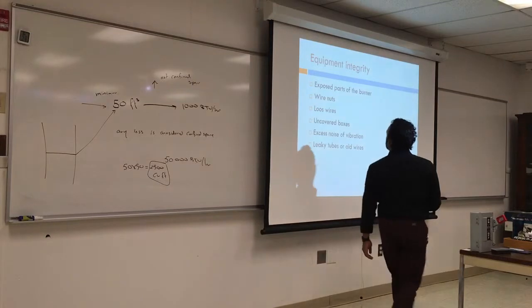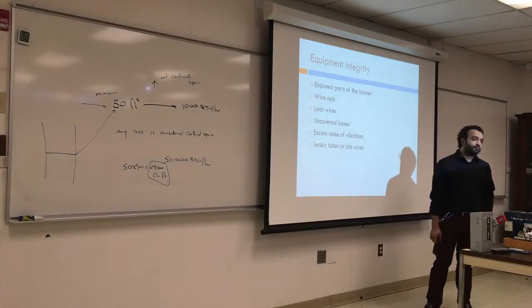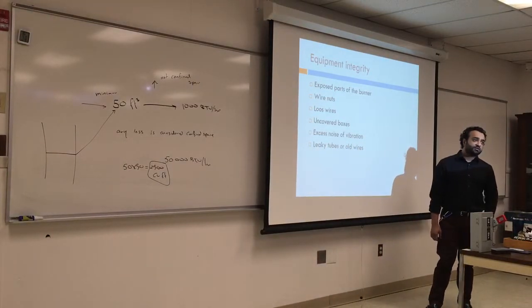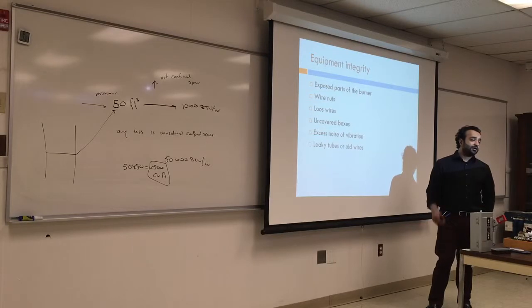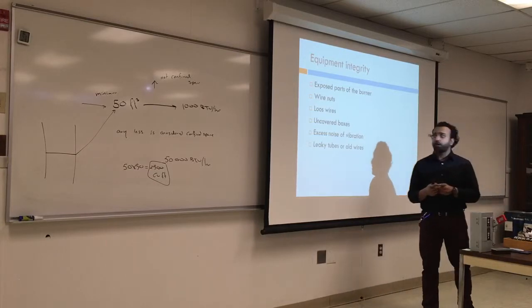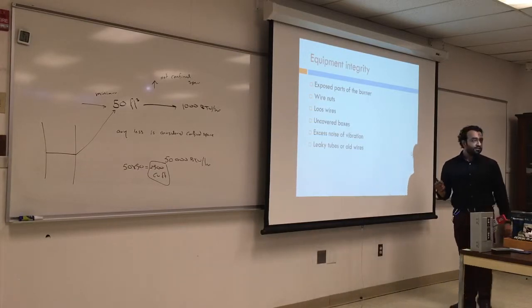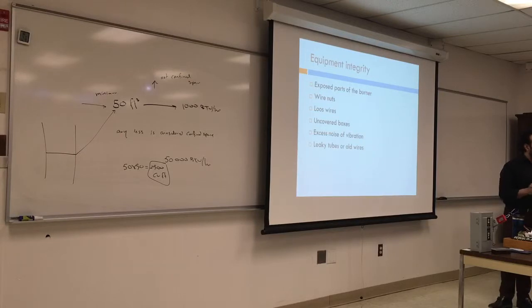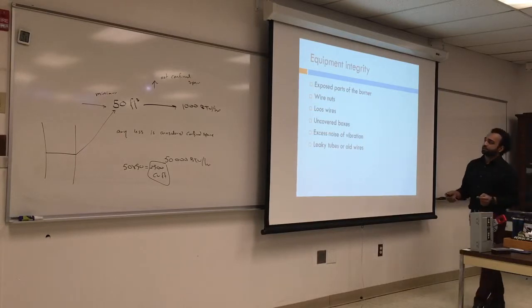Equipment integrity. Look for exposed parts of the burner. Everything should be covered in the right place. Wire nuts. We have experienced some issues with wire nuts. The wire nut is connecting 2 wires, but there's not an actual connection. Maybe the 2 tips of the exposed wire are not connected. Loose wires. You don't want the wire to be loose. Tug on each wire and ensure it's mechanically connected.